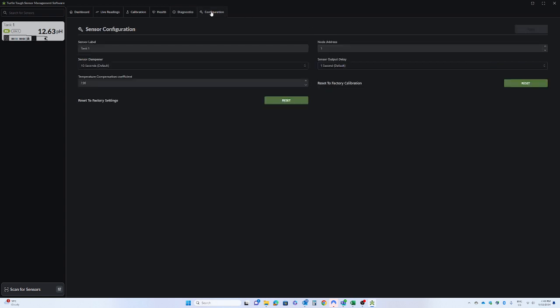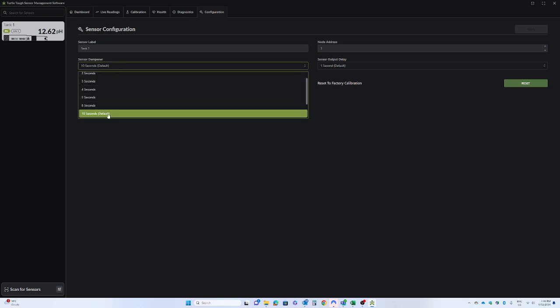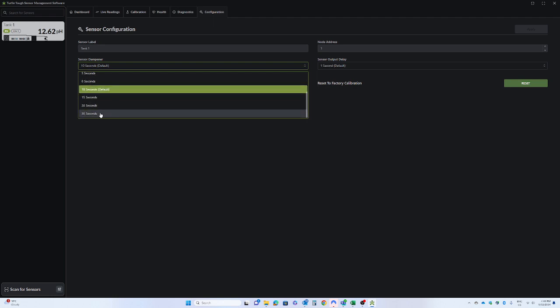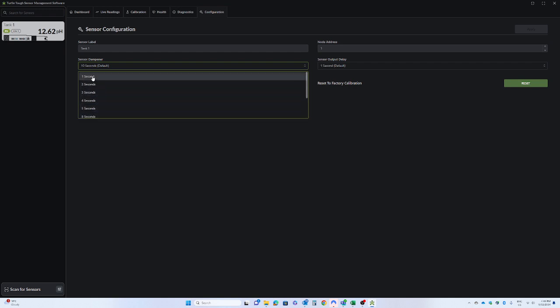And lastly, we have the configuration page. Some more information that you might find useful here. You can adjust the sensor's dampening, so the averaging of the data coming off the sensor. It is set to a default of 10 seconds. You may want to push that out to 30 seconds to smooth out the data. You can go all the way down to 1 second. We really only use that in the workshop and the laboratory for troubleshooting purposes, and we probably wouldn't recommend that in the field. Otherwise, the signal is going to be a little bit too noisy.